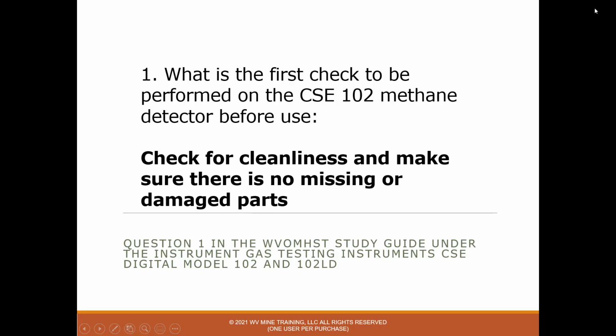So question 1, what's the first check to be performed on the CSE 102 methane detector before use? And the answer is just check for cleanliness and make sure there's no missing or damaged parts. You need to make sure it's in a permissible condition, make sure it's not damaged, make sure all the screws are in place, the seal or the gasket's there. You're going to take it in, and by the last open crosscut, it needs to be permissible.